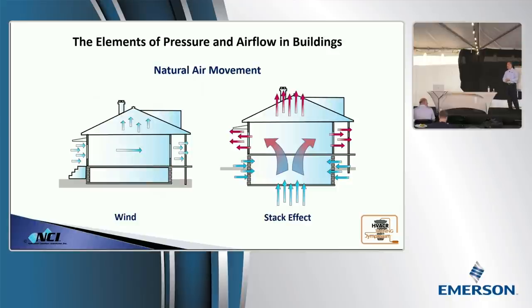Have you guys ever wondered why CO poisonings go up so drastically in the wintertime? What typically gets the blame? Furnace, right? Cracked heat exchangers. It's causing all those CO poisonings. Cracked heat exchangers are a defect, absolutely. But here's what I would submit to you. We're fighting a building problem more than we're fighting a cracked heat exchanger problem. The building is becoming the chimney. And guys, we're trying to fight it with equipment. You ever think about that?